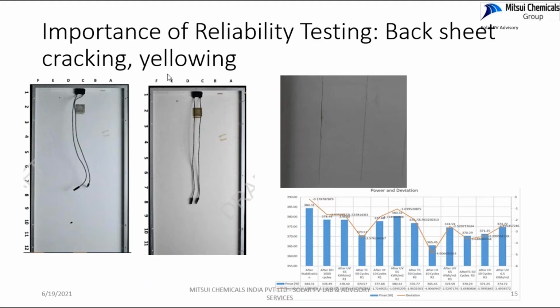Normal standard tests don't fulfill reliability - they can't reproduce reliability issues. So extended IEC reliability testing helps us get the life cycle or lifespan of the model. There are performance warranties and product warranties - without the product, the performance will not exist. So the product should first withstand accelerated tests and stress conditions.